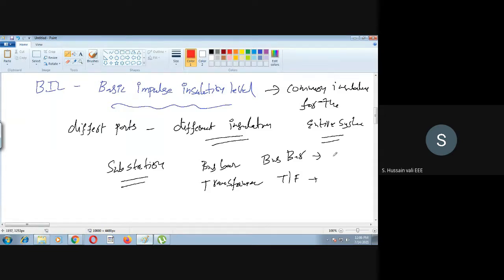Say for example, this is insulation number one. Insulation level in the sense, it's what is the highest voltage it can withstand. That's called insulation level. Whereas the other has another insulation level, with its own highest voltage it can withstand. But in the entire substation, not only these two, you have some more equipments also, so every equipment has a particular insulation level. When you take this whole substation, every part has a different insulation level.